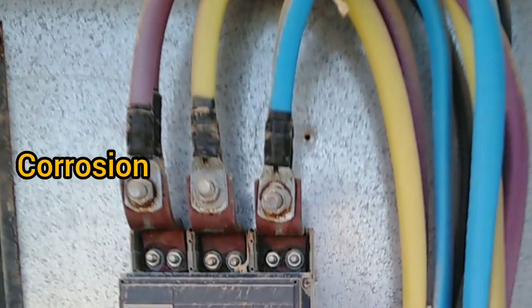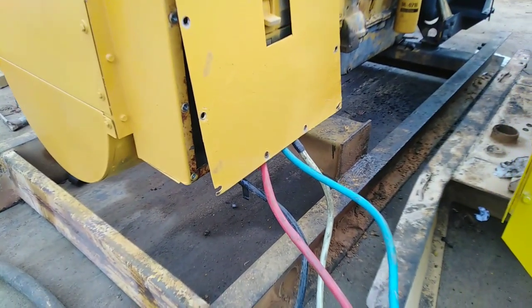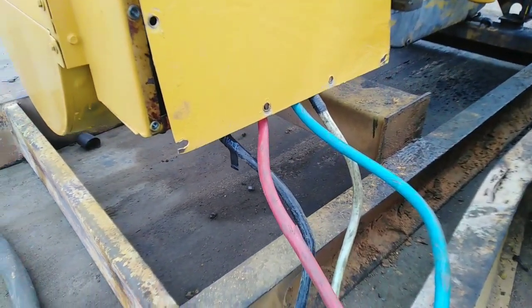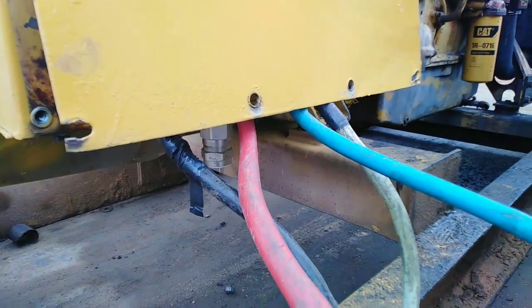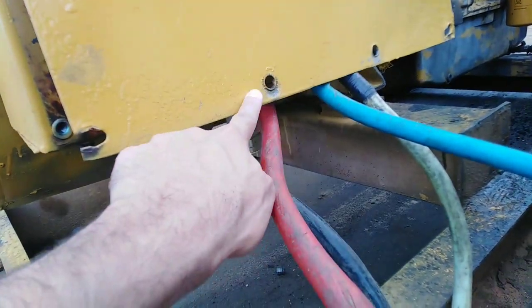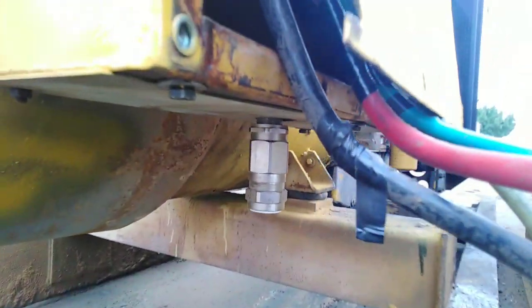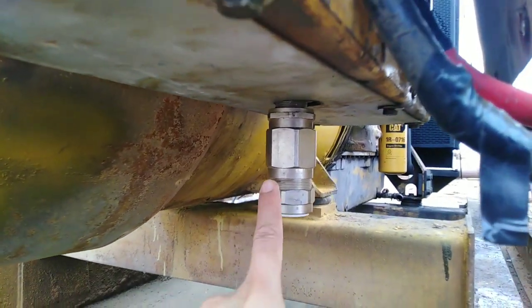Let's have another example in my workplace too. This power cable is connected to a generator. The cable enters under this heavy metallic cover. The error here is that when the generator runs, it vibrates. This plate can cut the insulation of the cable and cause a short circuit to the generator body, or between two phases. The cable entrance should be through a cable fitting.